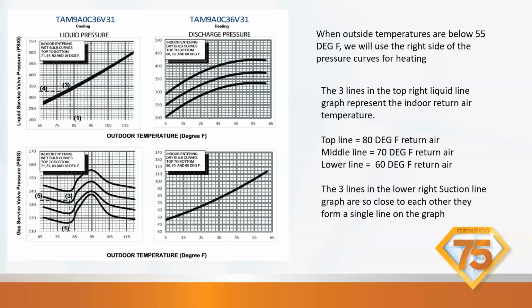So I do like to check that, because if it's 70 degrees inside the house and you're pulling in 50-degree air and it's 40 to 30 degrees outside, you might have some air infiltration pulling in from the outside, and then 50 degrees is not going to work properly through heating season. The three lines in the lower right, so this is the suction line graph, are so close that they just form a single line. So this graph has an 80, 70, and 60 just like this, but they're so close it just forms one line. So that's why you only see a single line.